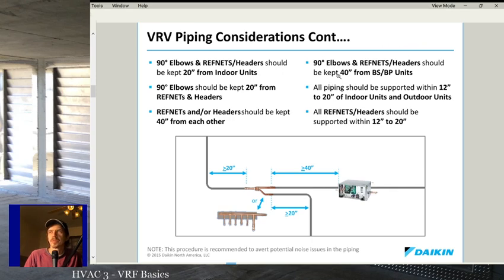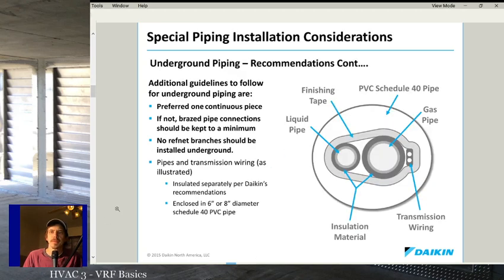Elbows and headers should be kept 40 inches from branch units. But again, this is kind of different from manufacturer to manufacturer. But your rule of thumb is 2 feet component to component is the least you go. And then for Daikin to the branch boxes, they basically say 4 feet. But these are your absolute minimums. All the pipes need to be insulated.